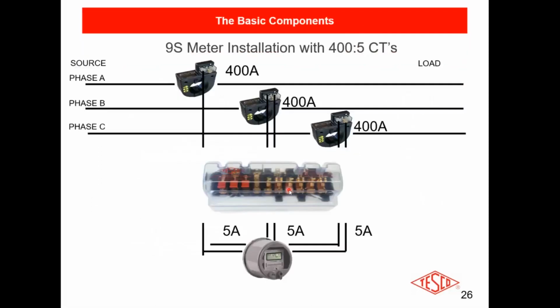Okay? What do I have? Well, I've got these three CTs here. Okay? These are instrument transformers. That means that they are precision transformers. And they do need to be tested, and they have to have a certain accuracy class to be considered instrument transformers. They've got to be at least 0.3 up through some burden. And when they say 400, it's actually implied that it is 400 to 5.